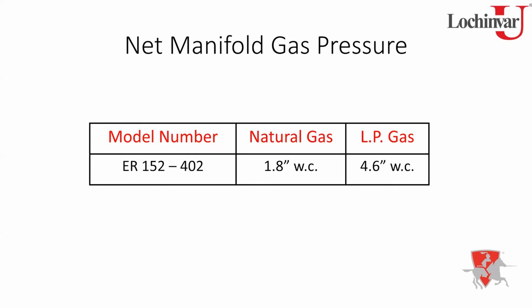So if I take 1.8 and add 1.4 to it, the gross pressure, or what I should be seeing coming out of that valve, would be 3.2 inches. You've got to do a little math here. Unfortunately, I'm sorry about that, but you've got to do the math. So I'm looking for 3.2 inches. If I've just got a single tube manometer hooked up to the outlet of the valve and that valve opens on a natural gas heater, 3.2 inches is what I should see, again, if that air is set at 1.4.